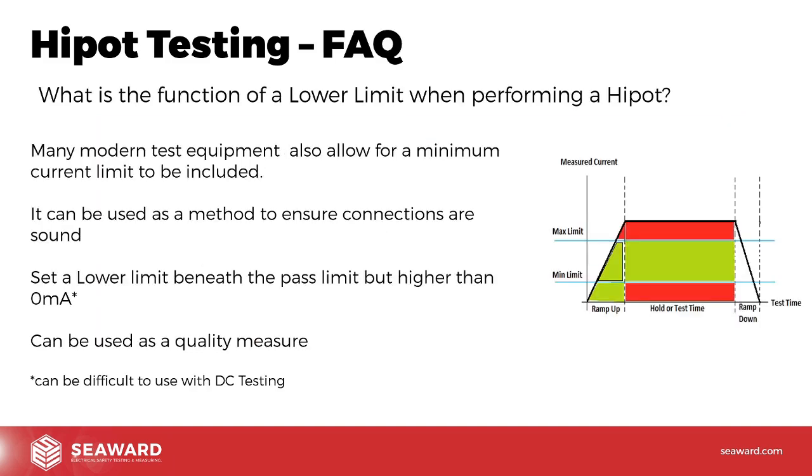What about a lower limit? Well, some Hipot testers, including all of the Seaward ones, allow you to set a lower limit when performing the Hipot test. But what use is that in terms of safety? Well, in many ways, it's not necessarily a safety function, but it is a good way of ensuring you have some definite connection to the product under test.